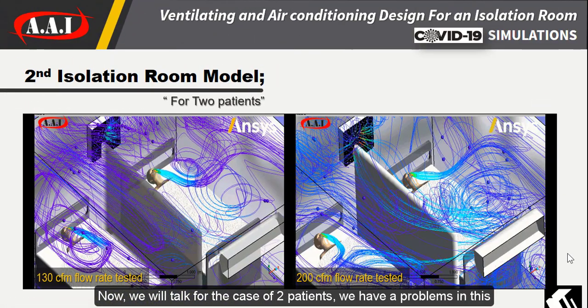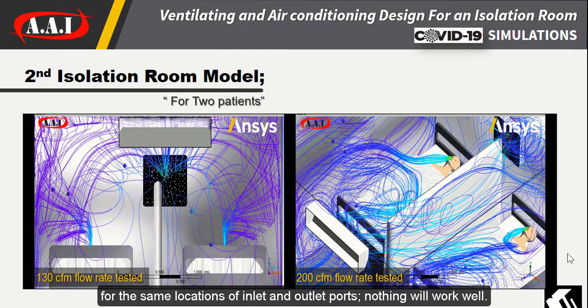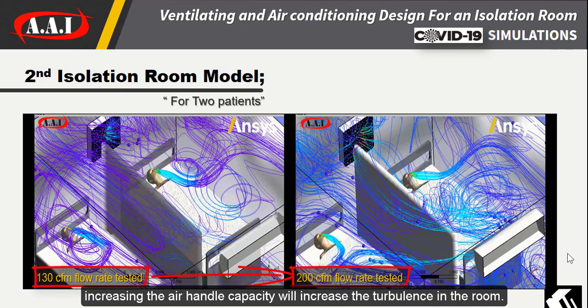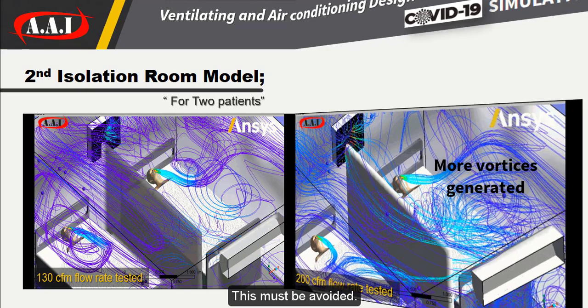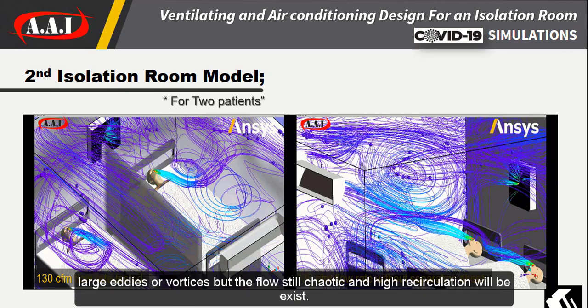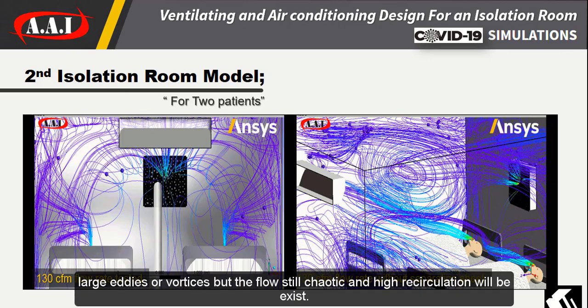For the case of two patients, there are problems with this model. For the same locations of inlet and outlet ports, nothing will work well. Increasing the air handling capacity will increase the turbulence in the room — this must be avoided. Also, placing a separation sheet between the patients will eliminate some large eddies or vortices, but the flow is still chaotic and high risk.